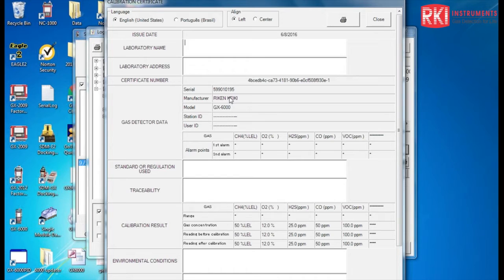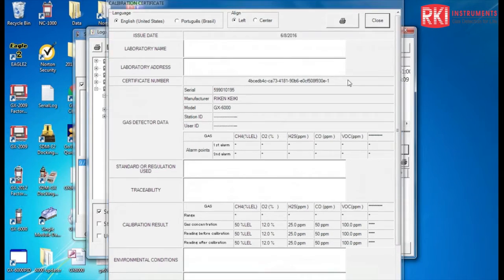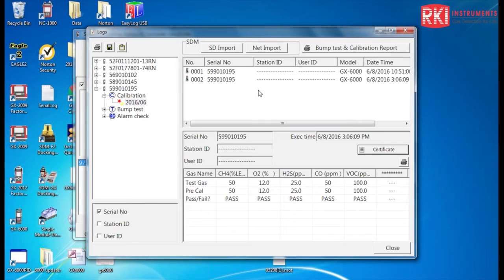Bruce, a question on the auto cal or the auto bump testing. In the example that you gave, they put it there on a Friday and then they want it done on Sunday so it's ready when they come in on Monday. I am assuming they still need to press the red button down on the instrument on Friday afternoon when they put the instrument in there, correct? That's correct, yeah, because that's what allows it to turn the instrument on at that time, and also that's what flows the gas to the sensors. So the only thing they have to do is put the instrument in and push that red button. That's it, and all the automatic settings will take over from there.